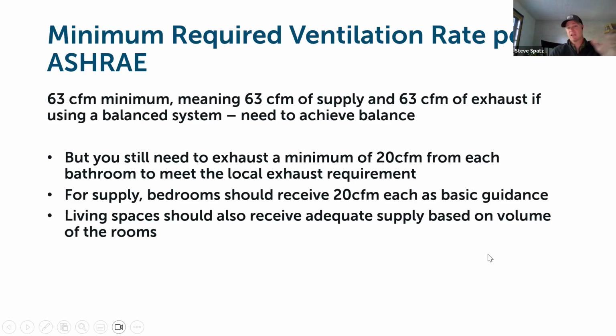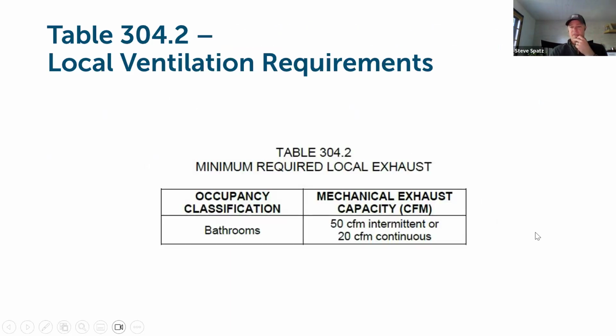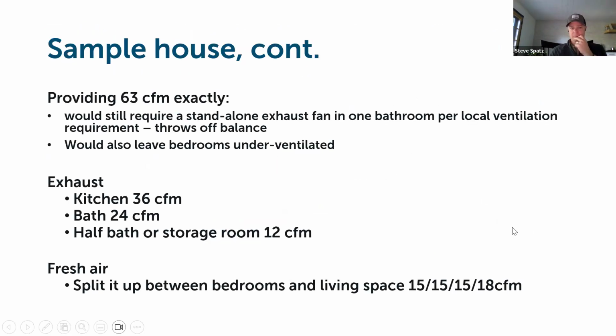So taking that into account of what the actual needs are of the house based on the number of bedrooms, occupants, and the bathrooms, we need to be considering that against that defined 63 CFM that came from the ASHRAE calculation. This is just referencing again those minimum requirements for the bathrooms. So if you only had a system set up to run and provide 63 CFM, you'd still be coming short in the bathrooms. And in this scenario, calling out that one option would be to put an exhaust fan in the bathroom to make up for that local ventilation requirement, but that's not a good practice, and we don't want to be going down that road. And you also would not be having enough air to move if you wanted to get to that same sort of 20 CFM average room by room for supply air throughout the building as well.